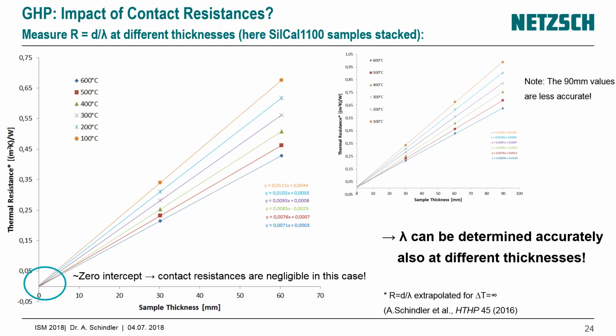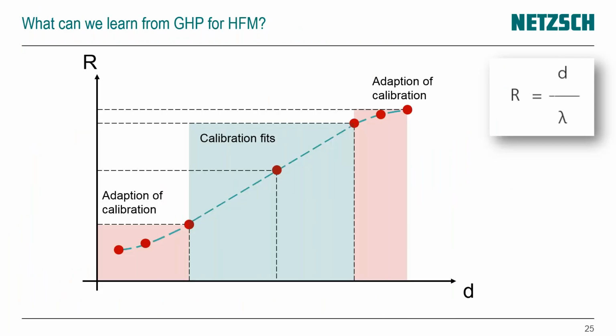So that means you can send us also samples. We do also contract testing on materials, and based on those materials where we can deliver a factory certificate, of course, you can also calibrate with. So that means if you look on this linearity check in the region where the function or the measurement R versus D is linear, the calibration fits to your material. If you leave the linearity outside of these ranges, that could be a sign that you need to adapt the calibration, maybe with a thicker or a thinner material, or different thermal resistances, different materials. But this gives you a first nice impression about the accuracy of your machine.